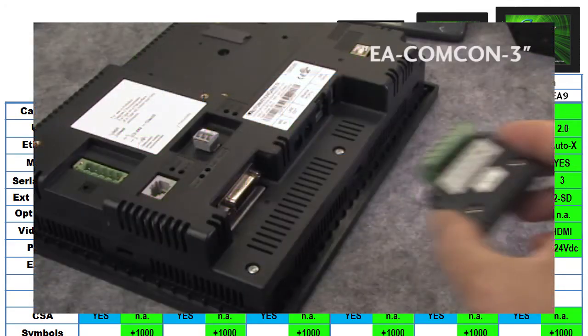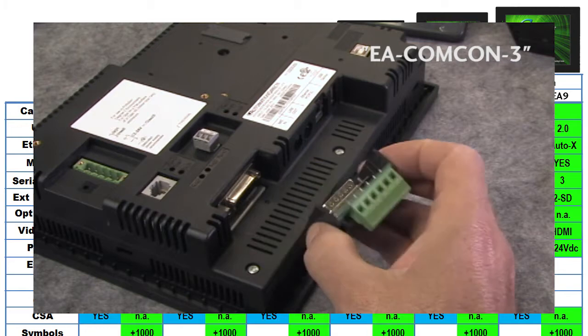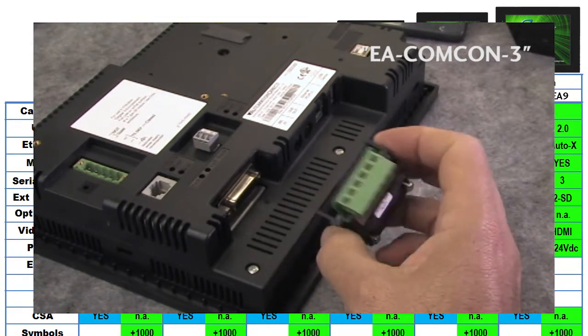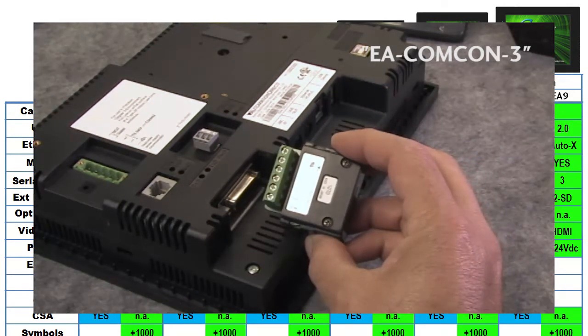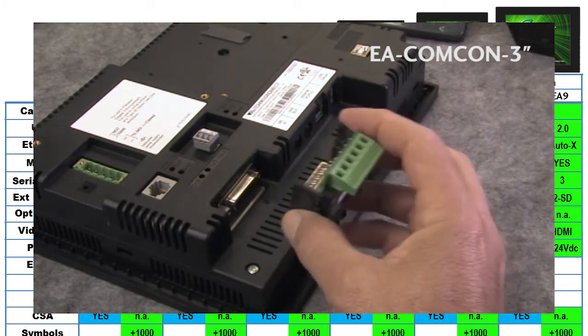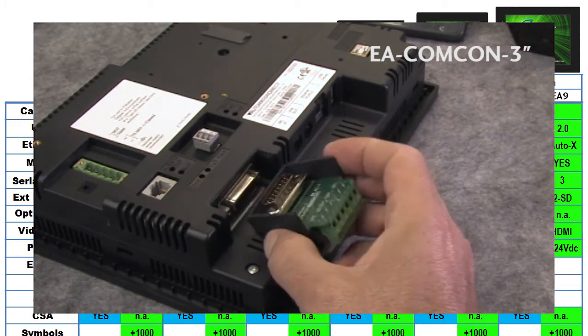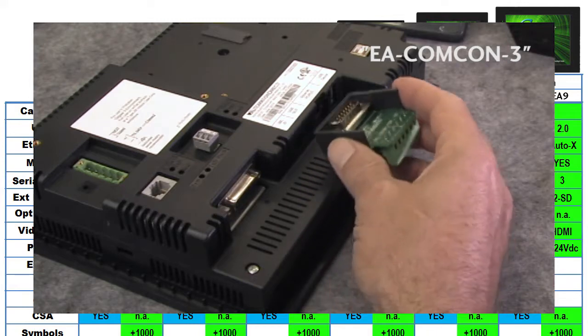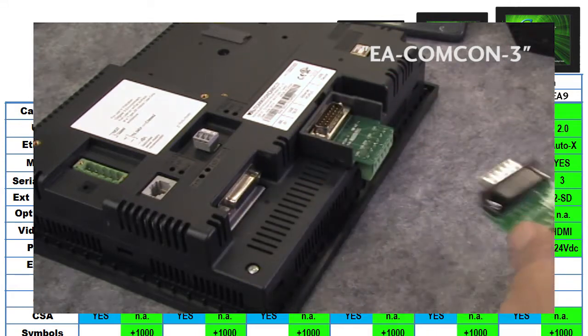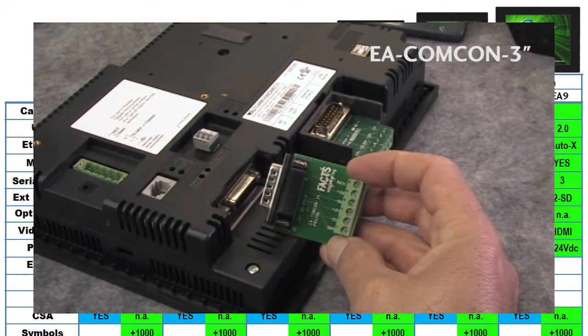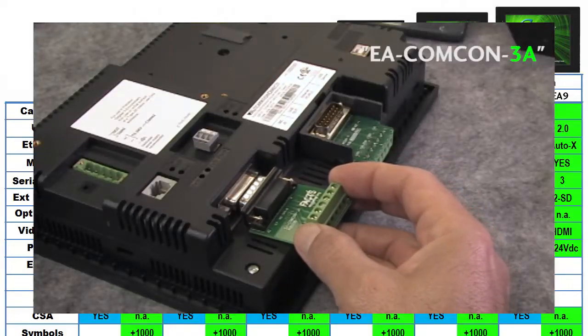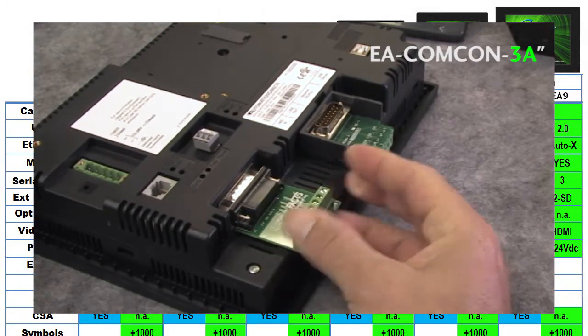The ComCon 3 serial port adapter that brings the 15-pin D-sub signals out to a 6-pin terminal block so you can wire up the 422 and 485 signals doesn't work with all of the EA9 panels because of the orientation of the D-sub connector on that adapter. The good news is, there's a new version of that adapter – the EA ComCon 3A. It does work with all the new EA9 series and it's half the price.